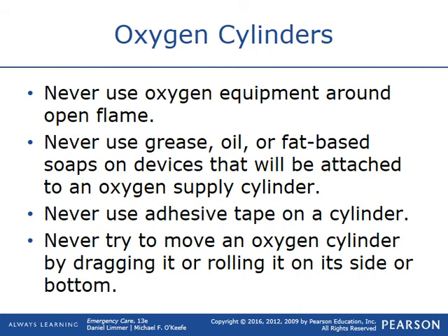Make sure that you never use oxygen equipment around an open flame. Never use any sort of grease, oil, or fat-based soaps on devices that will be attached to an oxygen supply cylinder. Never use any adhesive tape on a cylinder. And never try to move an oxygen cylinder by dragging it or rolling it on its side or bottom.